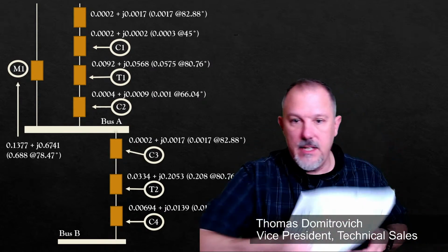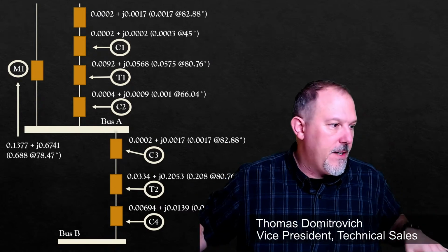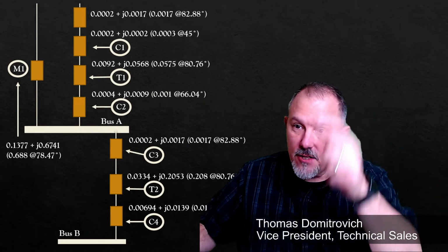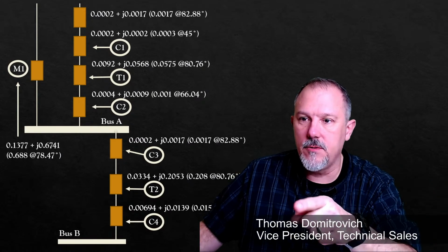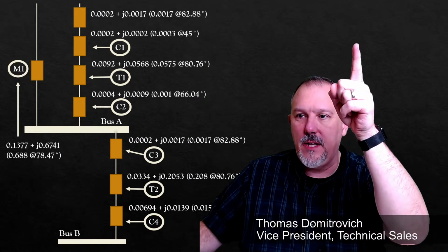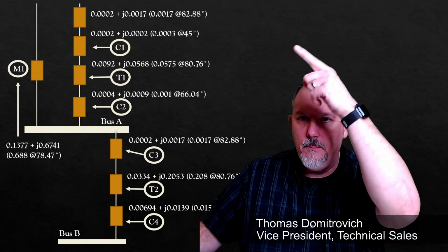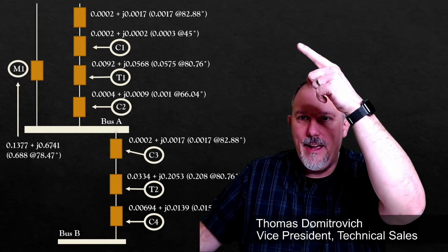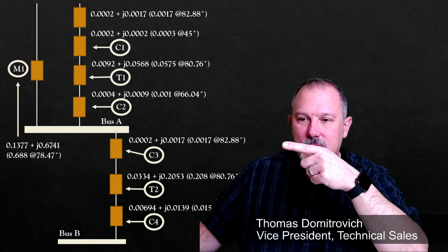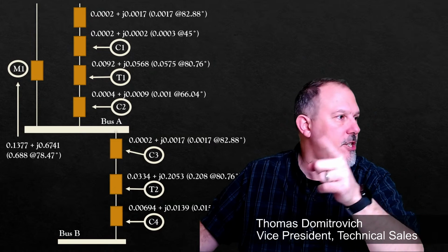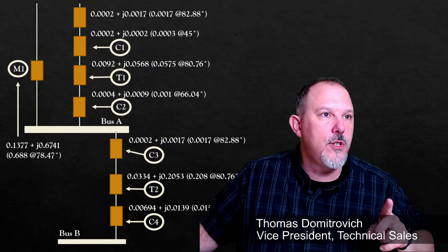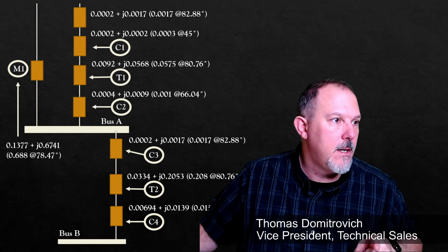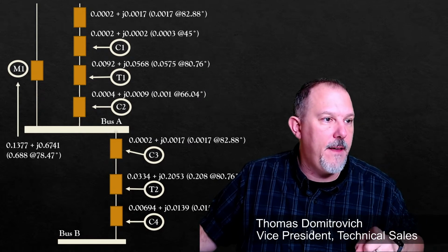We're going to take these impedance diagrams, and I have to fix the conductor 3 impedance. It is not 0.00. What I did was I copied the impedance of the utility, I must have copied it down for conductor 3 and I did not change it. So we are going to do that right now. I've got to make sure that that is correct.